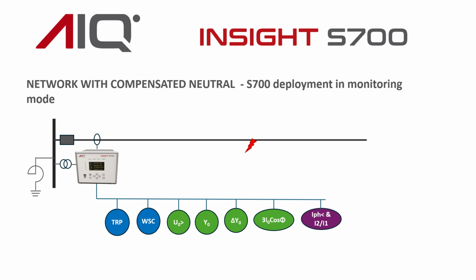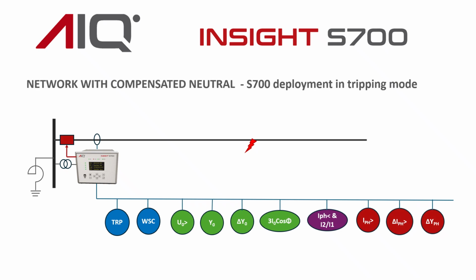Fault detection algorithms for systems with compensated neutral are similar to those with isolated neutral, except I0 cos phi now replaces I0 sin phi because of the strong active component of the earth fault current. The S700 in tripping mode for systems with compensated neutral is again similar to systems with isolated neutral, with I0 cos phi replacing I0 sin phi. Again, transient earth faults can be self-extinguished, but for permanent earth faults, tripping is available.